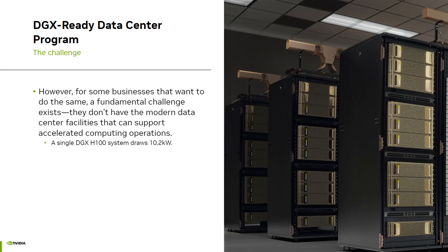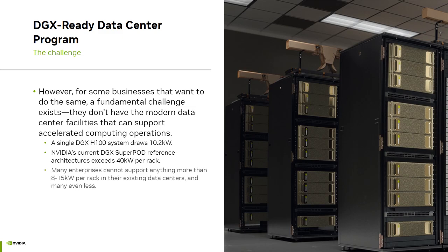A single DGX H100 system draws a maximum of 10.2 kilowatts. NVIDIA's current DGX SuperPod reference architecture exceeds 40 kilowatts per rack. Many enterprises cannot support more than 8 to 15 kilowatts per rack in their existing data centers, and many even less.